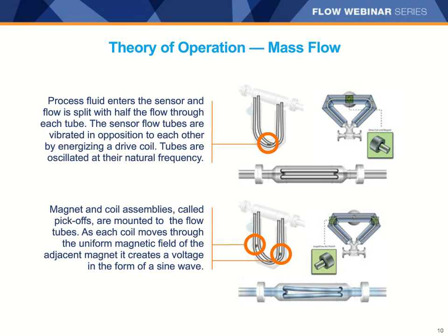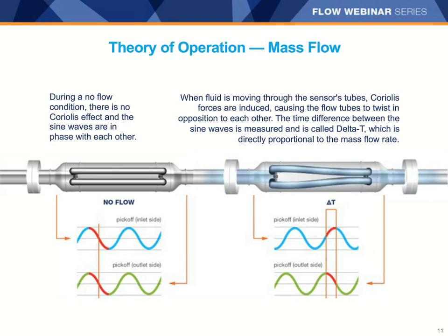When there is flow, the Coriolis effect on the tubes twists like what you see here in the bottom diagram. We measure that tube twist with magnet and coil assemblies called pickoffs. They are mounted to the flow tubes as seen in that bottom cutaway. As each coil moves through the magnetic field of the adjacent magnet, it creates a voltage in the form of a sine wave. So to summarize, during a no-flow condition, there is no Coriolis effect, and the sine waves are in phase with each other, as illustrated in the meter at the left. When fluid is moving through the sensor tubes, as shown on the right, Coriolis forces are induced, causing the flow tubes to twist in opposition to each other. That time difference between the sine waves is called delta T, or time delay, which is directly proportional to the mass flow rate.